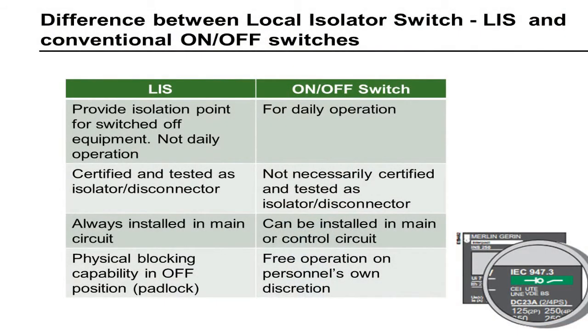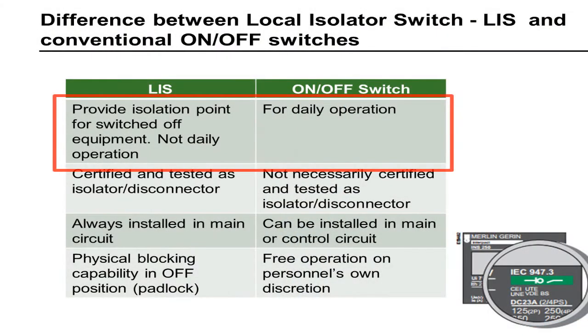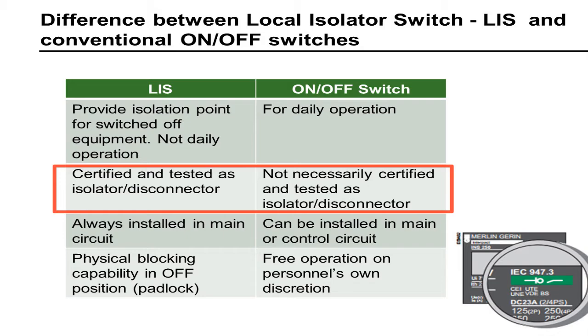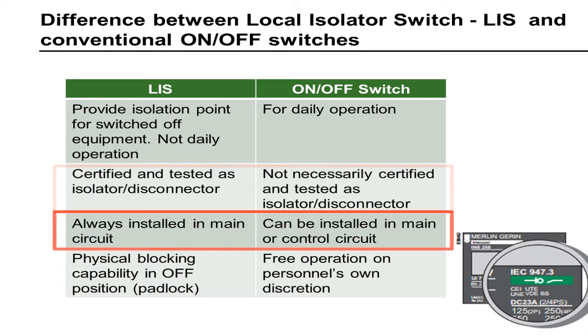Let's see what the major differences are between the local isolator switch and the traditional on-off switches. First of all, and most important, the isolation switch is used mainly for isolating the equipment, not for normal operational use. The on-off switches are for normal operation, for daily use. The local isolator switch is certified by the relevant national codes and standards, IEC and US standards, to be used as an isolating device. The on-off switches are not necessarily rated and certified as isolator switches. The isolators are always installed in the main circuit, never in the control circuit. The on-off switches could be installed in the control or in the main circuit, depending on the application.